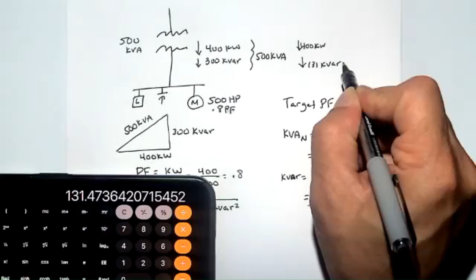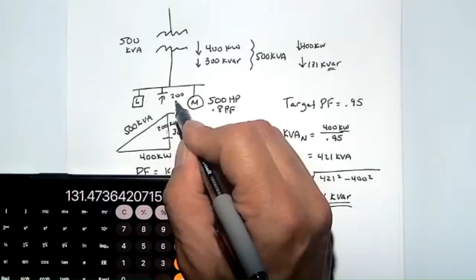But since we know our target power factor is 0.95, I can't go lower than the number I came up with. So I'm going to have to go higher. And so what I'm going to do is apply a 200 kVAR capacitor here, 200 kVAR to negate that. So that means I'm putting a 200 kVAR capacitor here. And what am I going to end up with?